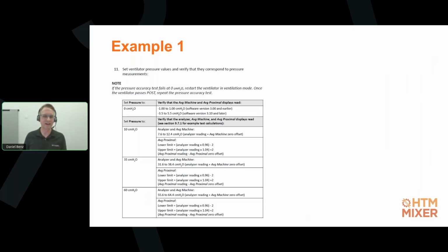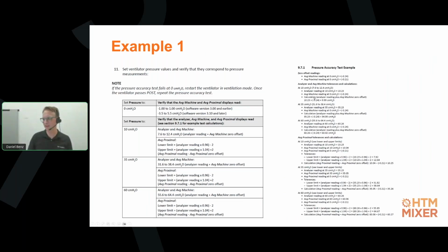That sounds very easy, right? But in this example, it turns out to be a bit tricky, and the instructions provided by the manufacturer are quite difficult to understand. So let's have a closer look. First, we need to read some values displayed on the ventilator at 0 pressure. Then we need to set the pressure to 10, 35, and 60, and compare what we measure with our gas flow analyzer. But here, the thing is, we need to calculate our limits ourselves. They saw that this is quite complex, so they also added in their appendix a calculation example.